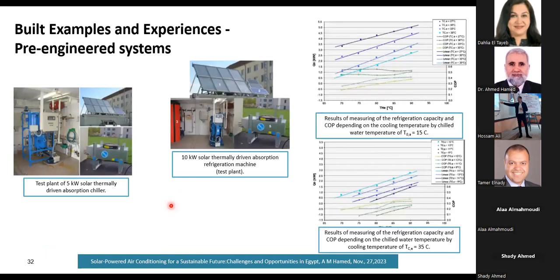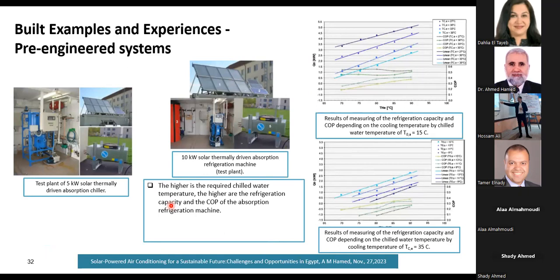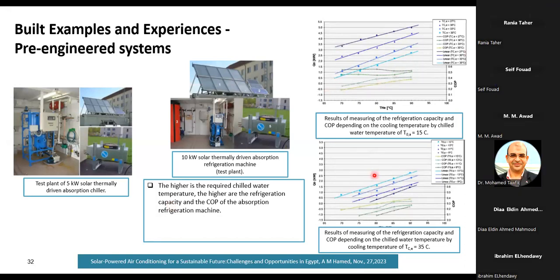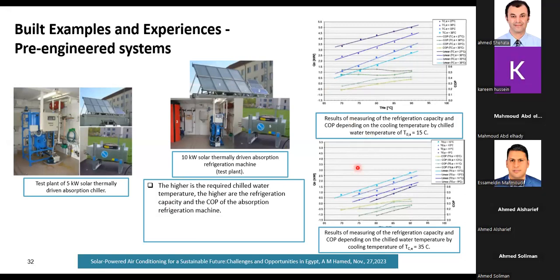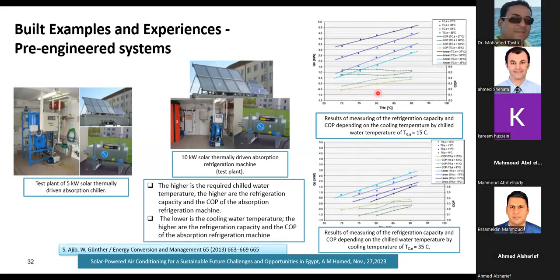From the point of view of the performance of this system, we can find that the higher the required chilled water temperature, the higher the refrigeration capacity and the COP of the absorption refrigeration machine. This coincides also with the performance of the vapor compression system.